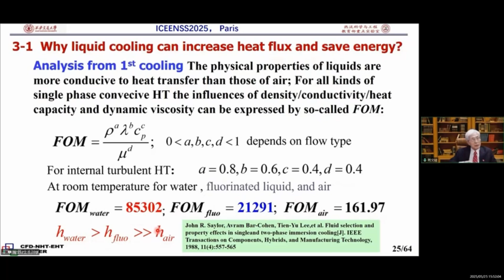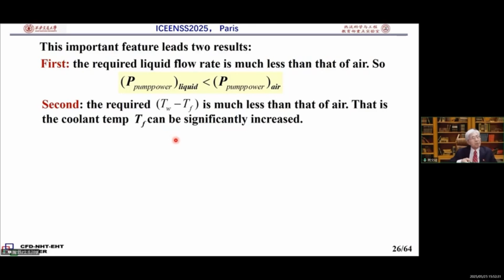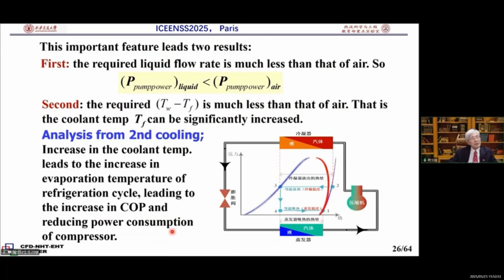Another effect is that the required temperature for liquid cooling is much less than that of air. Therefore, TF can be increased, say, from 20 to 30 or 40s. Then, because the TF is cooled by the second cooling, which is a refrigeration system, the condenser and evaporator can work at a higher temperature. We know that an increase of condensation or evaporation temperature will increase COP. That reduces the consumption of compressor power. Therefore, because of these two reasons, liquid cooling can save energy.